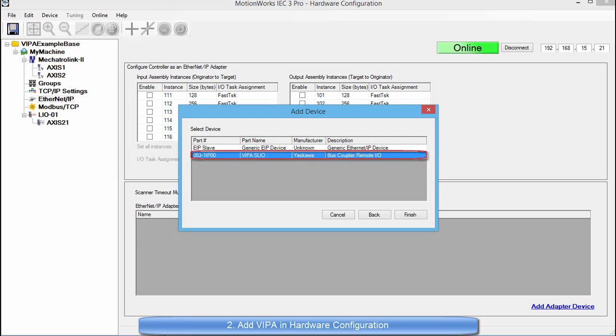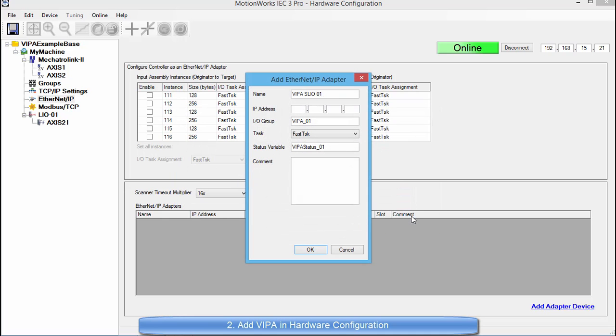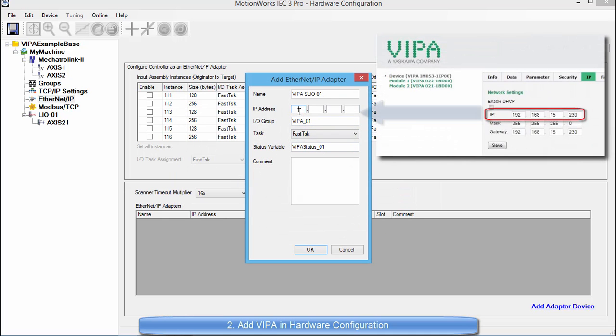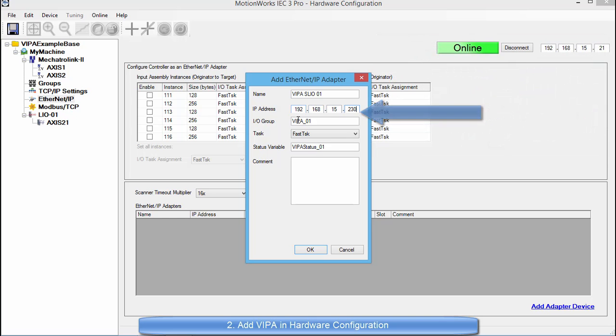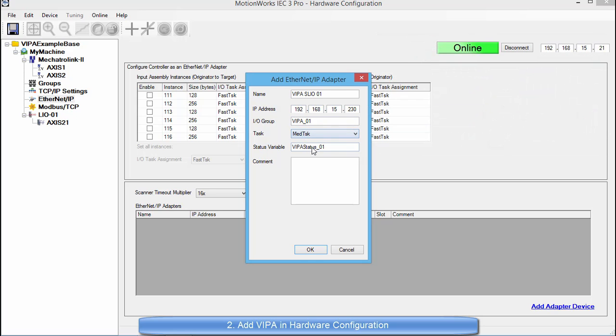First I am going to set the IP address that is the IP address of the actual VIPA SLIO system. For me it will be 192.168.15.230. And then I want to make sure that I set this to either the medium or the slow task because there is a limit to the task speed that is supported by VIPA.